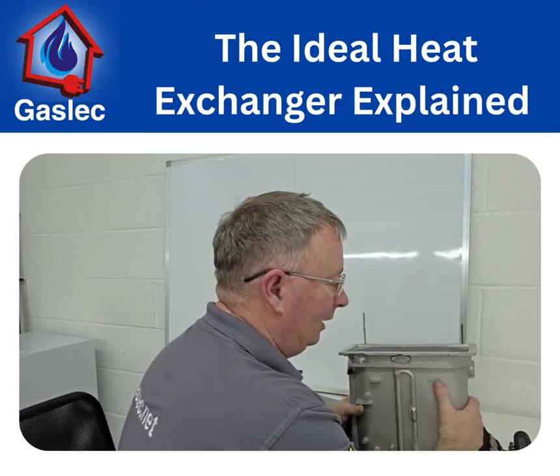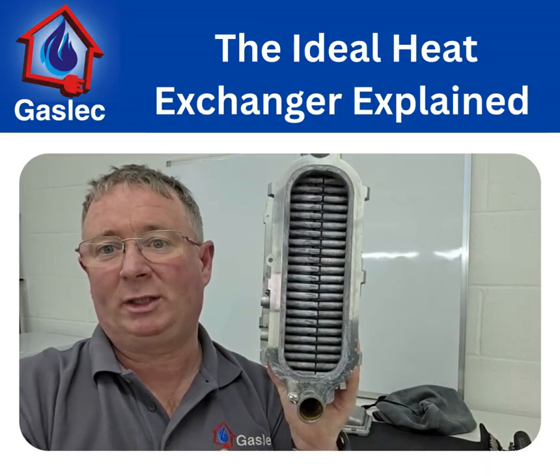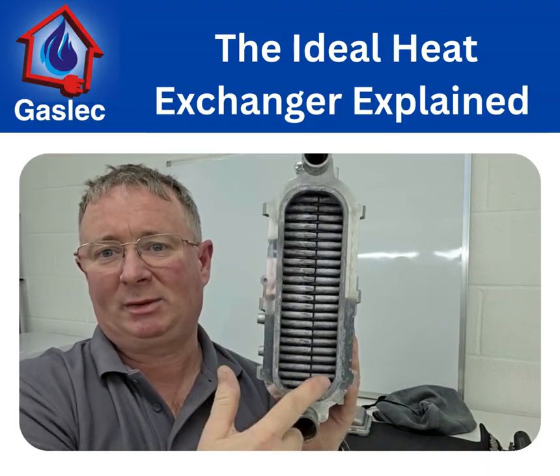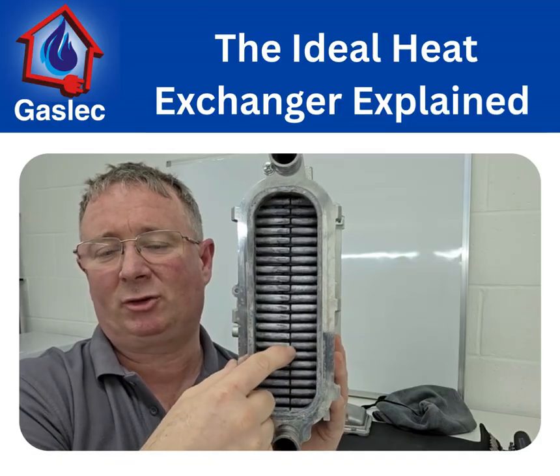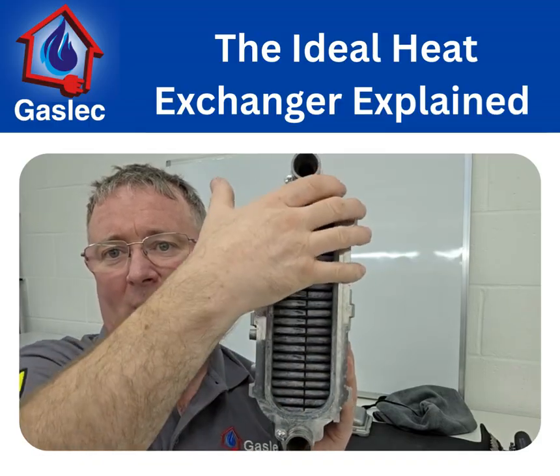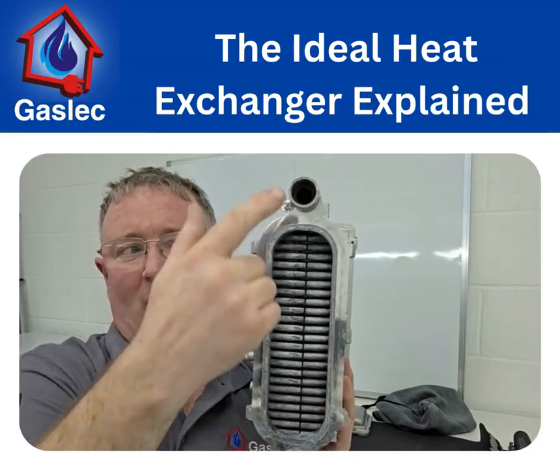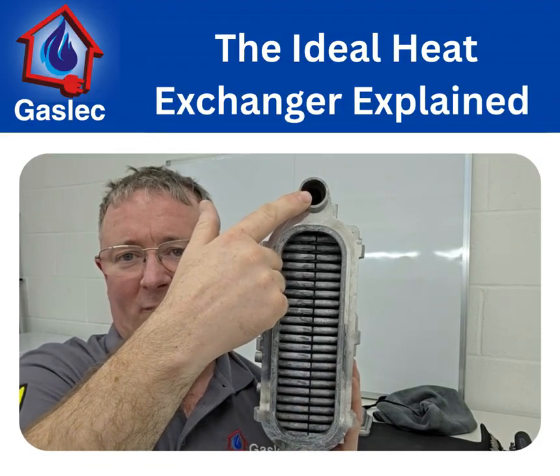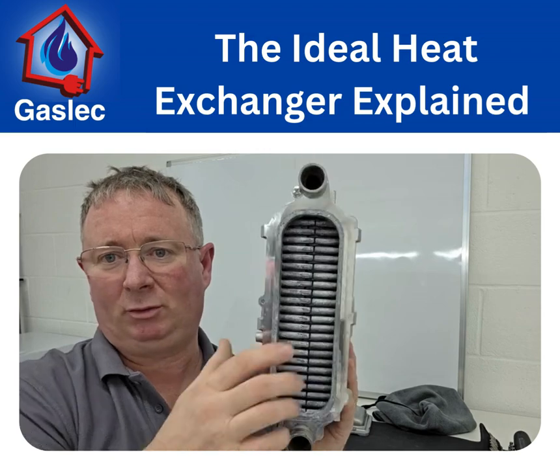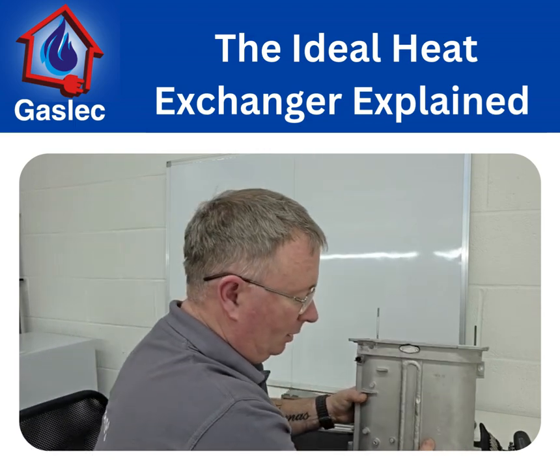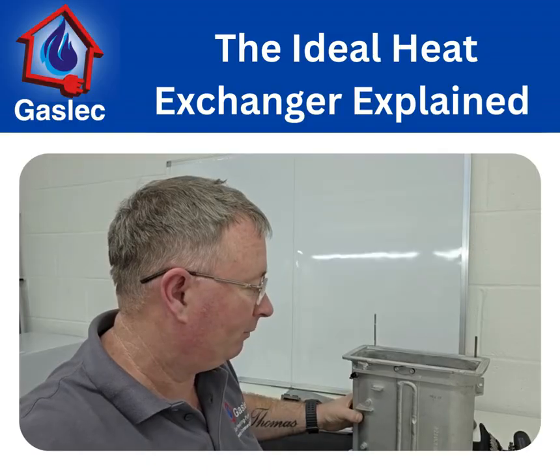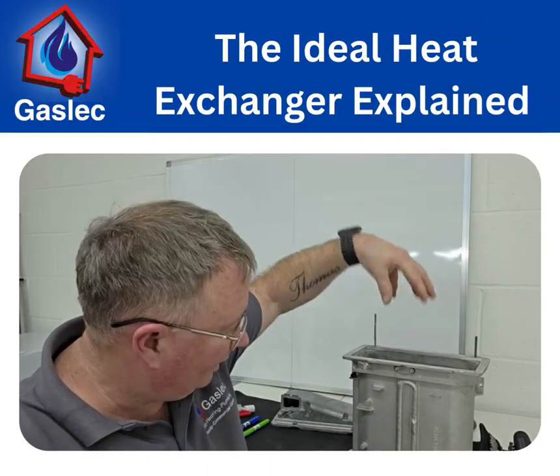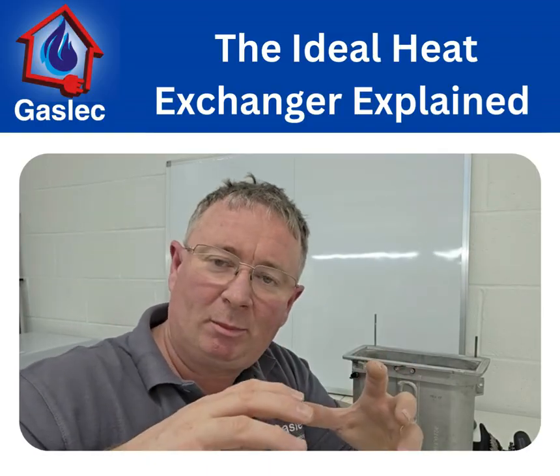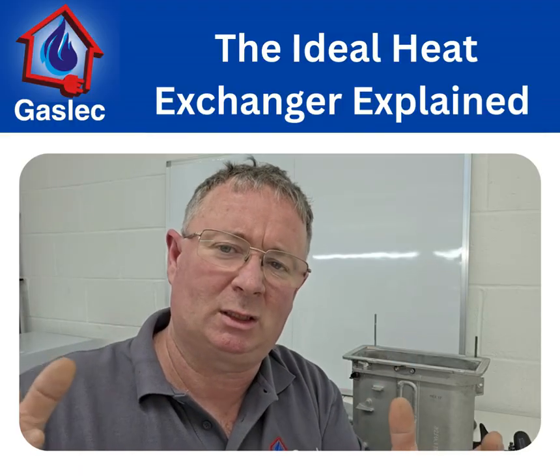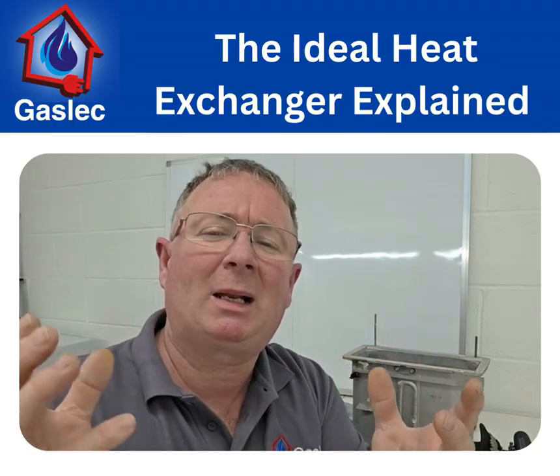As the flame comes down and the condensed water is produced, it comes out at the bottom here. We can see they're almost touching, so there's not a lot to pass through, and at the bottom here is a big sump, and that's the water that comes in from the pump, and that's it off to the system now. So it's a downward firing boiler. It fires the heat down through the bottom, and it comes out of the bottom into what we call the sump, which is this last big lump of plastic.